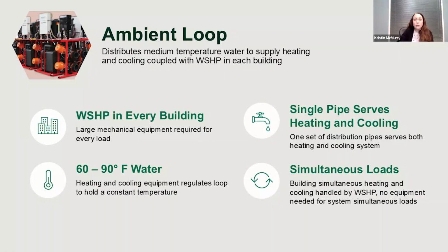Now, what technologies can provide that heat? Heating is always the harder one compared to cooling. Those air source heat pumps that could only go to a certain temperature can now go lower and provide a better COP. So air source heat pumps often become a big player here. You no longer need a chiller, you can run purely from a cooling tower.